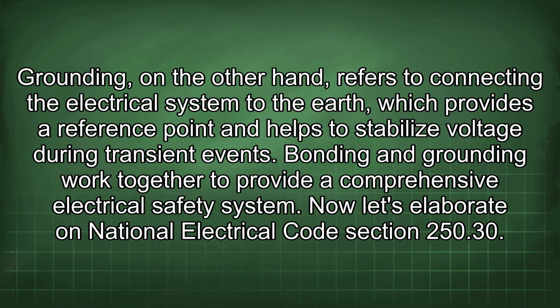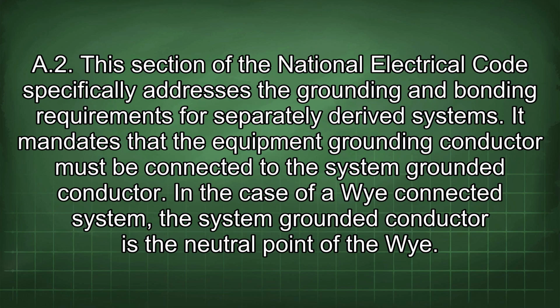Grounding, on the other hand, refers to connecting the electrical system to the earth, which provides a reference point and helps to stabilize voltage during transient events. Bonding and grounding work together to provide a comprehensive electrical safety system. Now let's elaborate on National Electrical Code Section 250.30(A)(2). This section of the National Electrical Code specifically addresses the grounding and bonding requirements for separately derived systems.